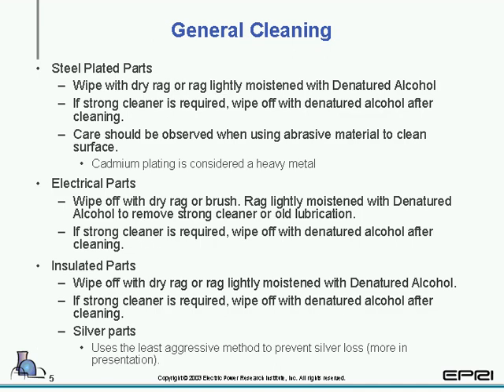So. Next slide we're going to take a look at is general cleaning. When cleaning for most of PMs, you'll see that for the steel-plated parts, the electrical parts or the insulation parts are basically the same. You're going to wipe with a dry rag. If that will not remove whatever chemical is on there, you can use denatured alcohol. If you use any other cleaner that is more aggressive than denatured alcohol, you're going to want to go back over it with denatured alcohol to remove whatever residual chemical could be left upon the breaker. But as far as preventative maintenance only, just use a dry rag.